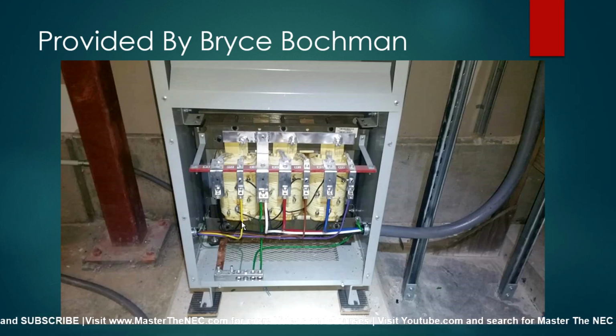So let's look at some transformer example. This was provided by Bryce Bochman. Now, Bryce, you'll notice here, I don't see over here. I think, yes, he does have a lug here. So he's actually running his equipment grounding conductor through and then down. I think if you punched this hole, Bryce, you wouldn't have needed to do that. Over here, you do it again. Because this is probably, looking at the nature of it, flexible metallic conduit. A liquid tight flexible metal conduit in here.